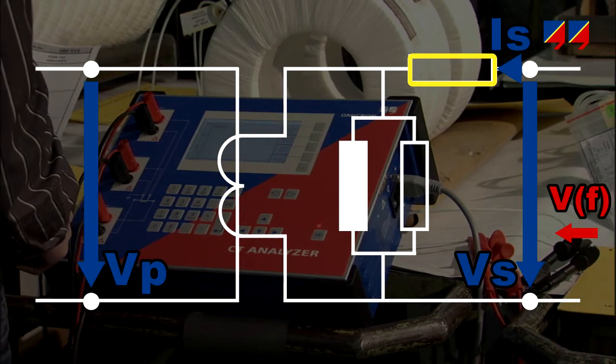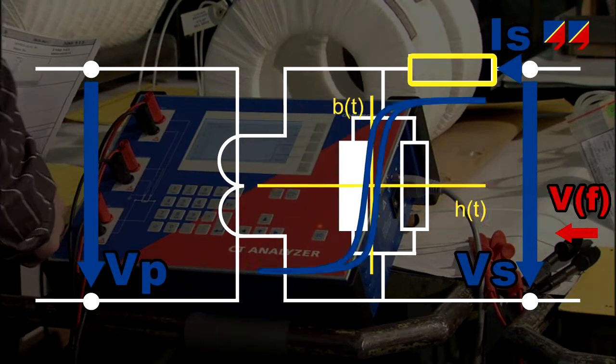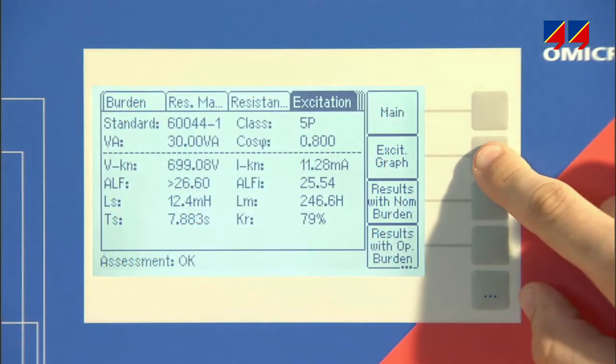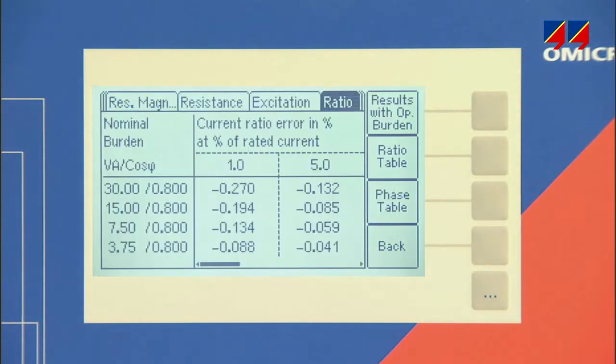It measures the DC winding resistance, the excitation curve, and the turns ratio, determines all the parameters of the CT model, and displays the accuracy data for all current and burden values.